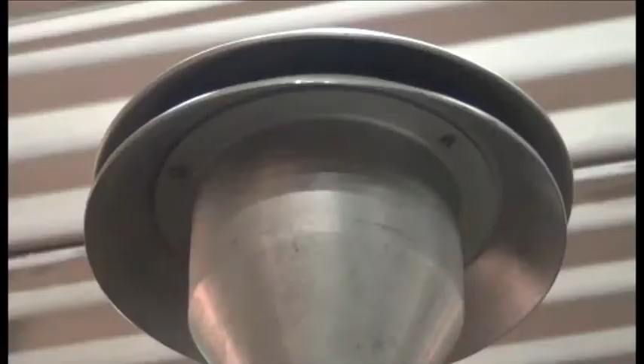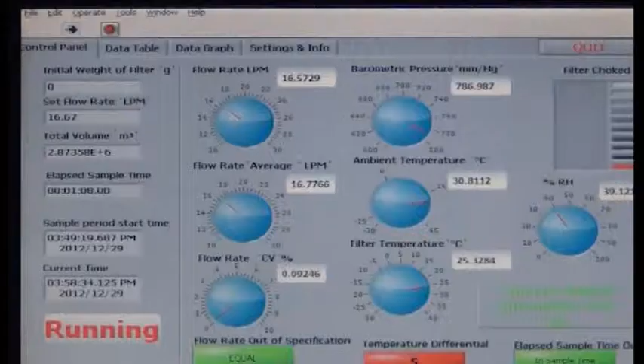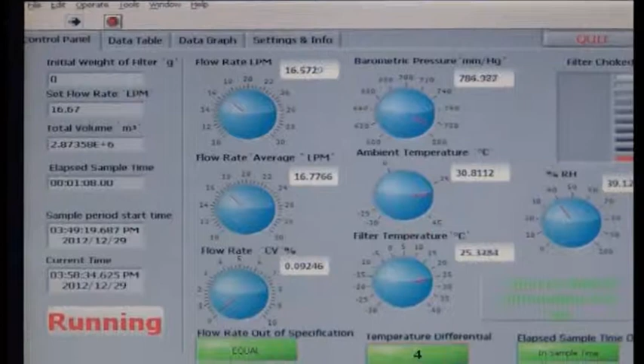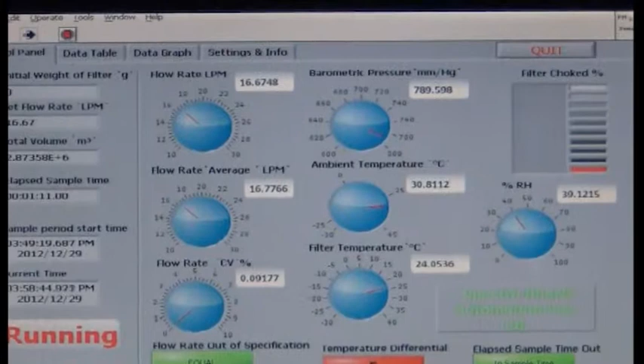The sampler is designed according to US EPA 40 CFR 50 Appendix L. The top plate and wind deflector have been designed for a sampling flow rate of 16.67 liters per minute and are unaffected by wind direction and wind speed of ambient air. The system includes a common PID controller, AC drive and a simple PC.